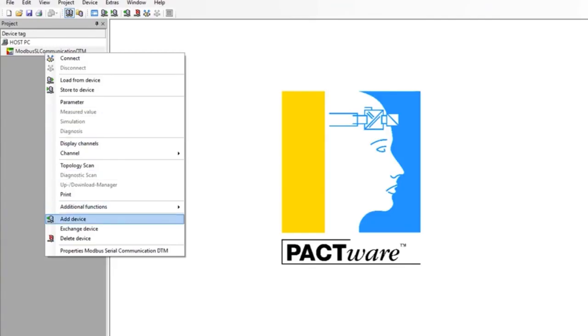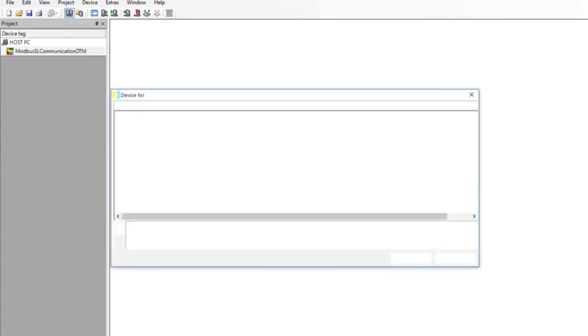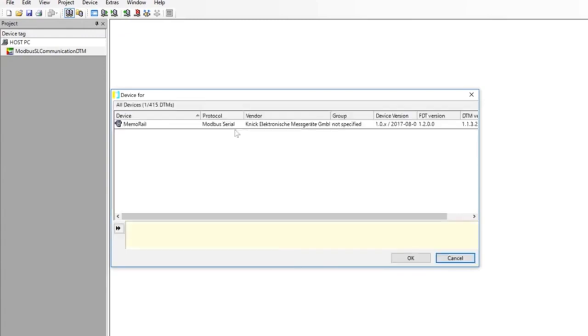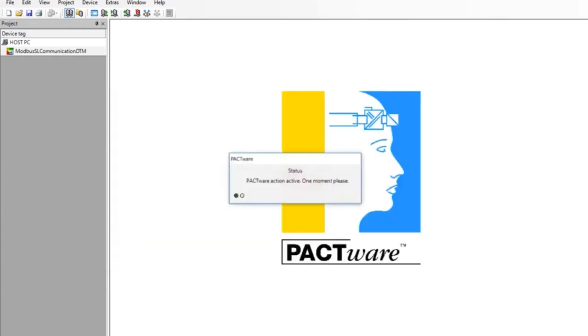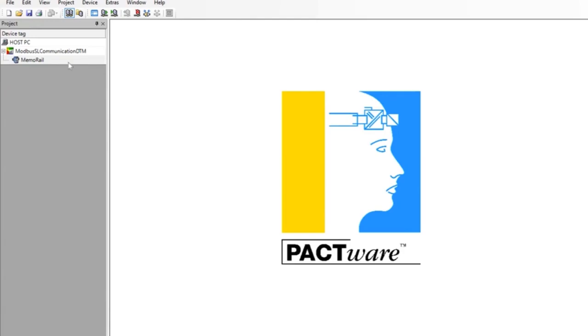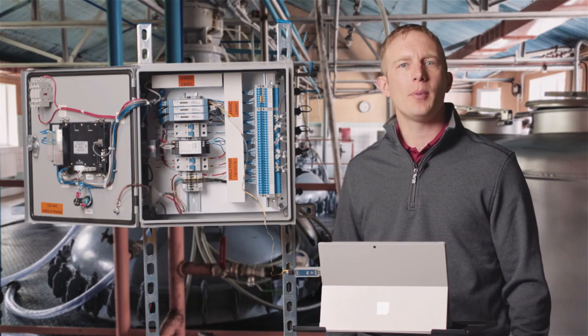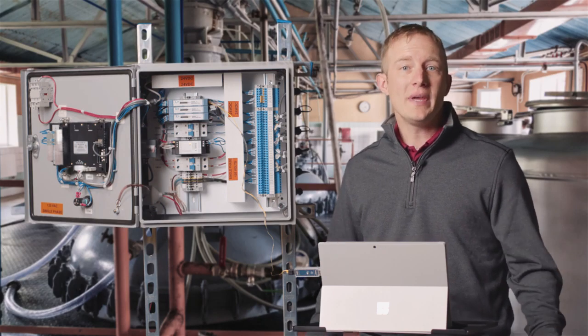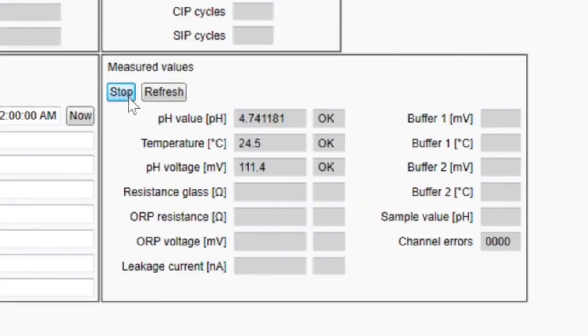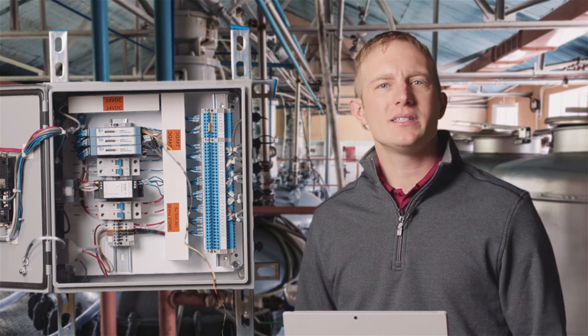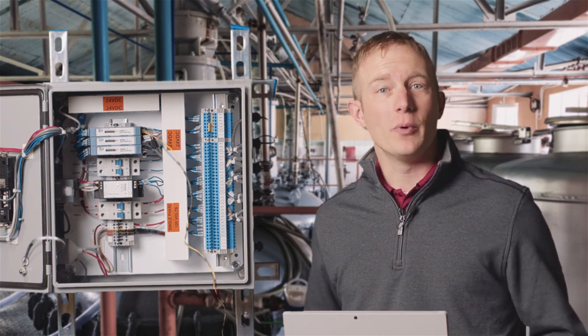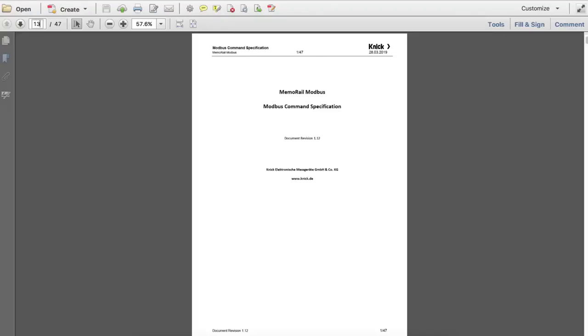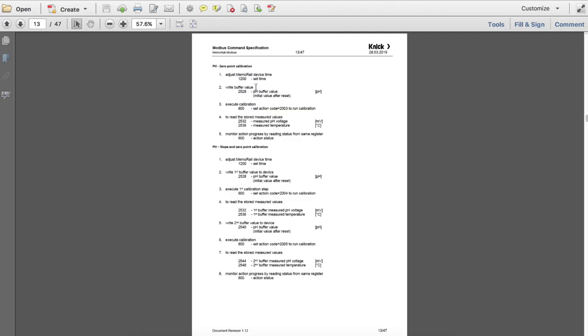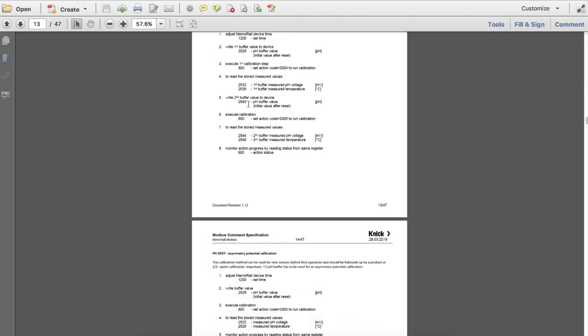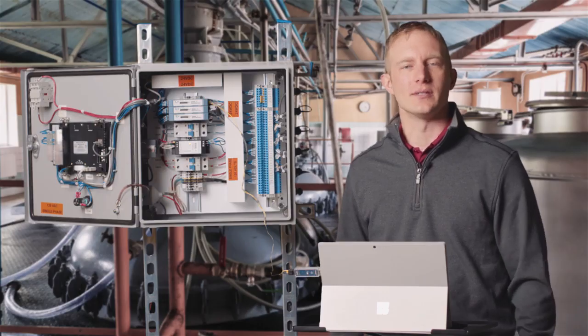We'll now connect to our MemoRail by establishing communication to the device through our DTM framework. We're utilizing Pactware in this example. Once we've established communication and have brought up our MemoRail DTM, we'll begin reading our measured value registers and ensure there are no Modbus channel errors. If you're utilizing a system other than a PC with the DTM, you can find these read registers in the Modbus command specification file. It's now time to calibrate our pH sensor.